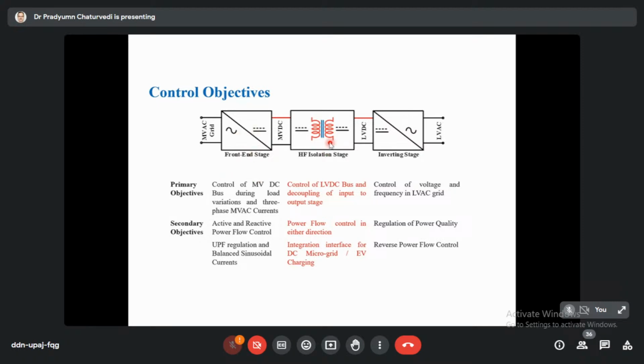The stages are front-end converter, isolation, and inverting or load end. The primary objective of the front-end stage is to control the medium voltage DC bus during load variations and three-phase MVAC currents. Any disturbance at the load side will come to this DC bus, and source side disturbance will come through the AC bus. So this rectifier will control the DC bus voltage and improve supply current power quality in terms of harmonics and power factor: DC bus regulation, its ripples, supply current harmonics, and supply current power factor.